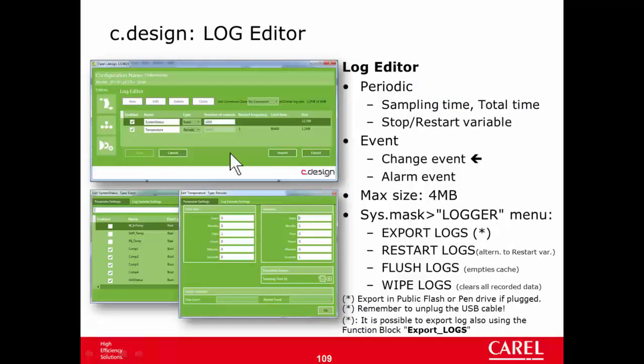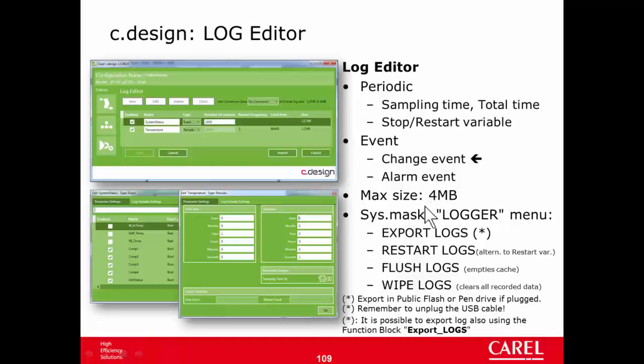That's all. So there are two types of logs, periodic and event, maximum four megabytes. It is possible to export using system menu or function block. And regarding function block, this is a very powerful option because since there is limited space for the logs, the export logs allows, for example, to export the logs of the last day every midnight. It is possible to export in the internal memory that is 90 megabytes, and in the last controller it is possible also to extend it. So if the strategy exports the logs of the last day every midnight, it is possible to have the history of the temperature, for example, for the whole life of the controller. That's all also for the logs. Thank you for watching.